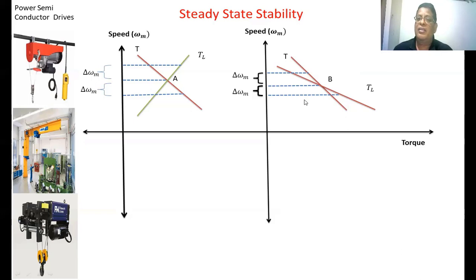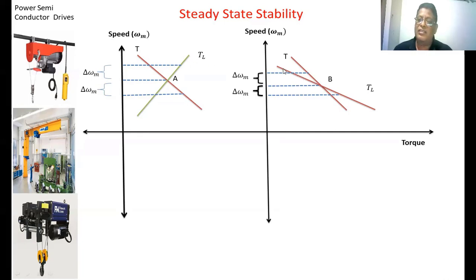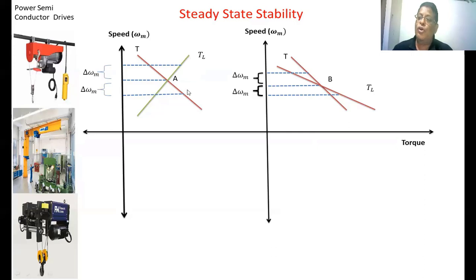So this system becomes an unstable system — this system does not have steady state stability. This is one way in which we can analyze whether the drive system is stable or not at an equilibrium point. In the graphical method, it requires the speed-torque characteristics of the motor as well as the load. In the first case the load torque characteristic is one type and in the second case it is different, and the first case system is stable but in the second case the system is unstable. When the speed is decreasing, if the rate of change of load torque is less than the motor torque, the system is stable.